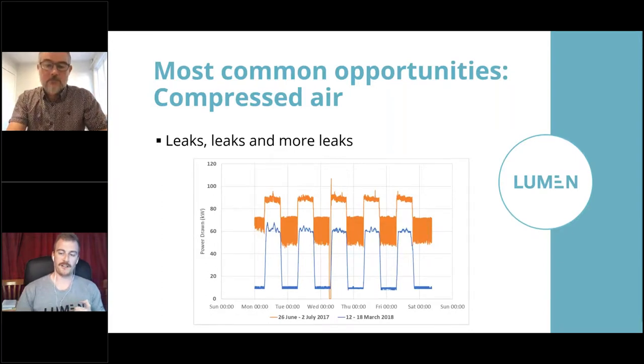But we've been on a lot of sites where they haven't actually fixed the leaks, and the tags are still there from, say, 2016. The other option is to turn off any compressed air required, or any equipment that requires compressed air, and just leave the compressor going. You may need to submeter it to see what the load is while you've got no load on it. Or some of the newer compressors have got screens that you can actually see what the load is.